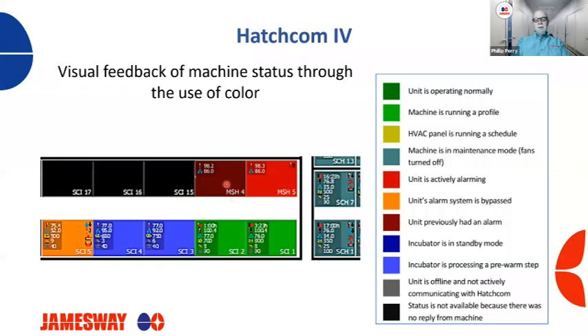And then if we see this maroon color, this would notify us that this unit, number four, has been in alarm, but it's recovered and it's running normally. And you would have to open it up and silence it like you would a platinum machine. And we'll look at how to clear some of our alarms. But anyway, these are just a very good visual.